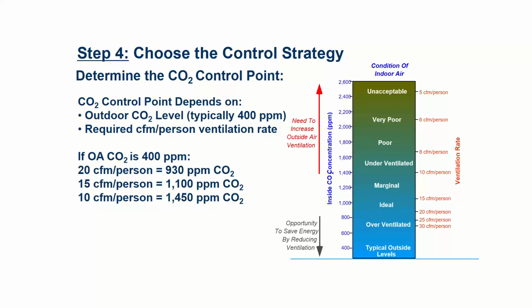So for most spaces, let's say for an office building, what I want to be is 700 parts per million of CO2 above the outdoor air level. In most areas of the country, I'll see like 450 parts per million. Now, if I'm in a densely urban area like Boston, Chicago, New York, whatever, maybe I'm going to have more like 500, maybe 520, something like that. But for most places, suburbia, if you will, I'll have 450 parts per million of CO2 outside. I want to be 700 above that for my set point. So my set point becomes 1150 parts per million.